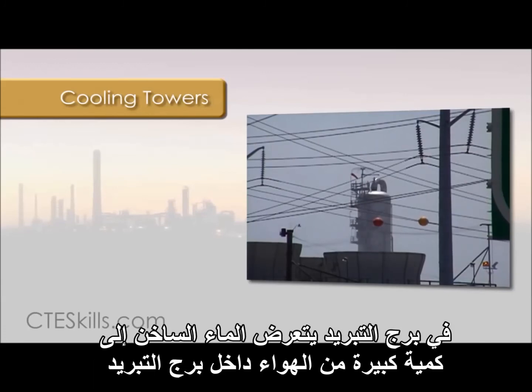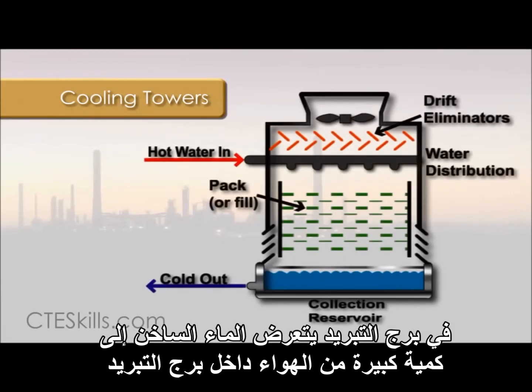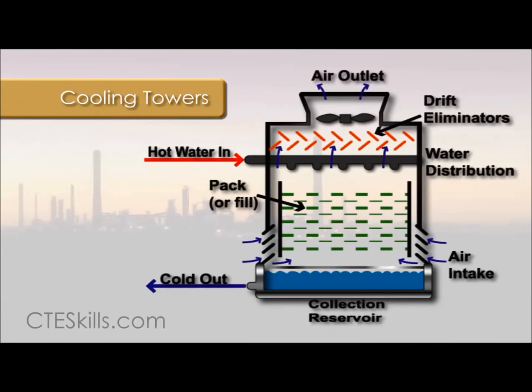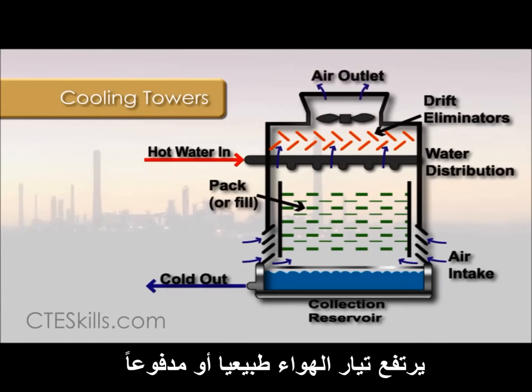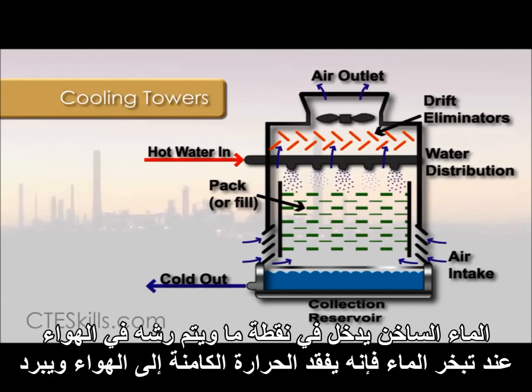One example of an air-cooled heat exchanger is a cooling tower. In a cooling tower, hot water is exposed to a large volume of air inside the cooling tower. A current of air rises by means of natural or forced draft, and hot water enters at some point and is sprayed into the air. As the water evaporates, it loses latent heat to the air and is cooled.